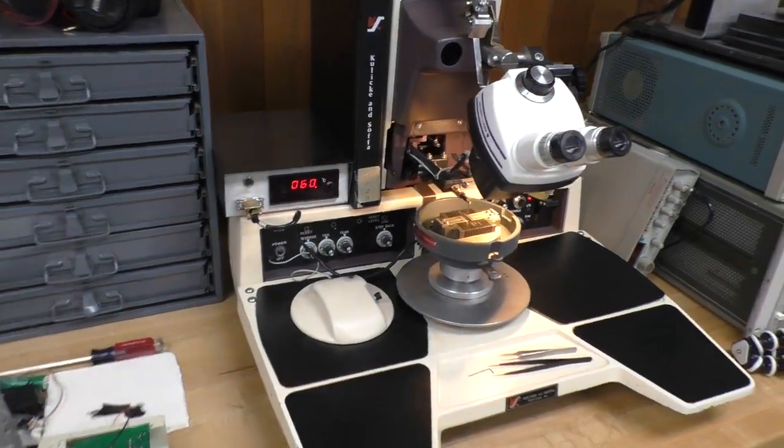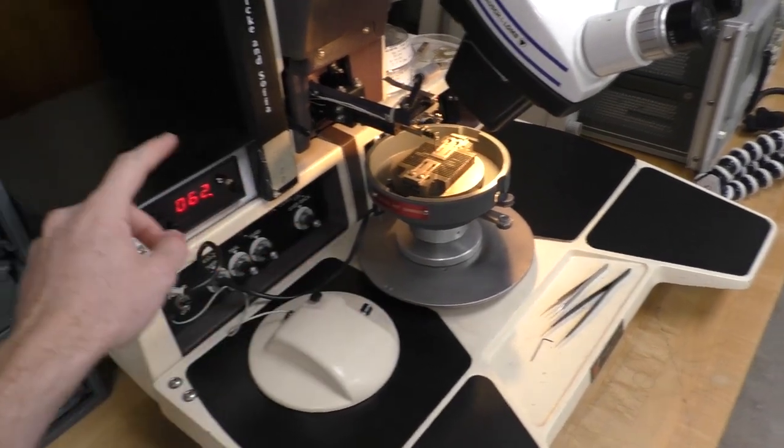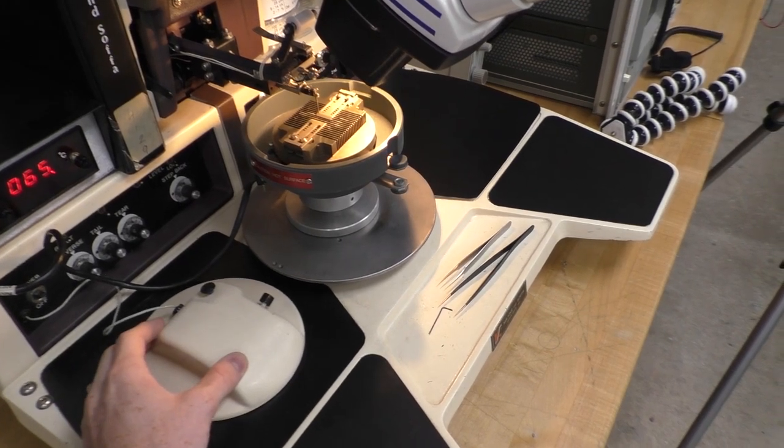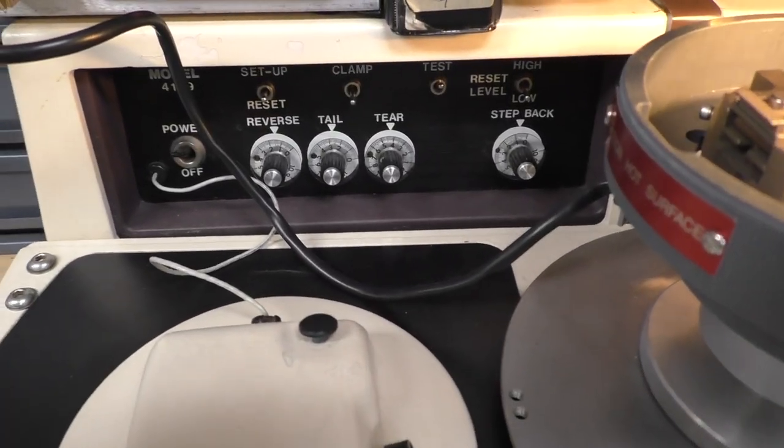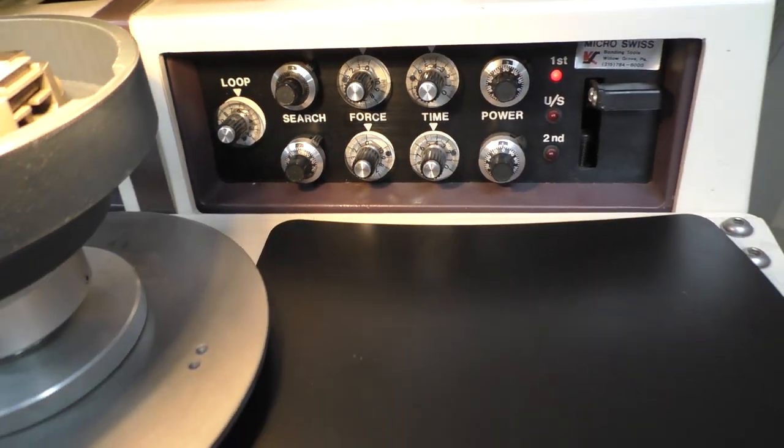Remember, as I said before, this is the work holder where your chip goes, and this is the power supply for that heater. This is the mouse, which is sometimes called the chessman, and that allows you to manually move the stage. There's a number of controls for the various settings and power, force, and time of the bond parameters which have to be tweaked.